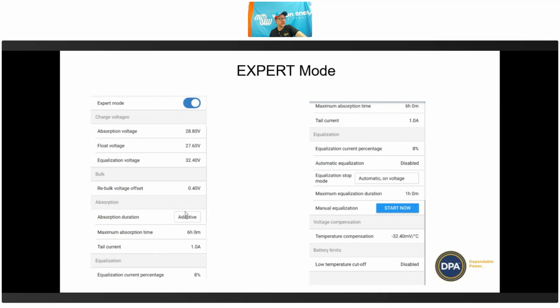This is basically determining when it's going to go back into absorption. So when you have a charge algorithm, you're going to charge the battery all the way up to, say, over here we've got 28.8, and when it reaches 28.8 and has finished putting as much current as it can in at that voltage, then it's going to stop charging and hold it at 27.6, which is our float voltage, right? It's not going to go, oh, I'm below 28.8 and go back up to 28.8 again. It knows that it's in float, and it's just going to hold it at 27.6.